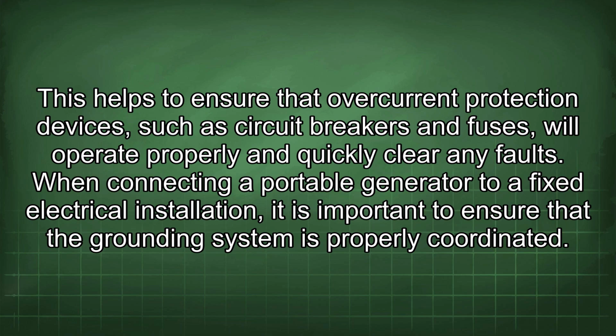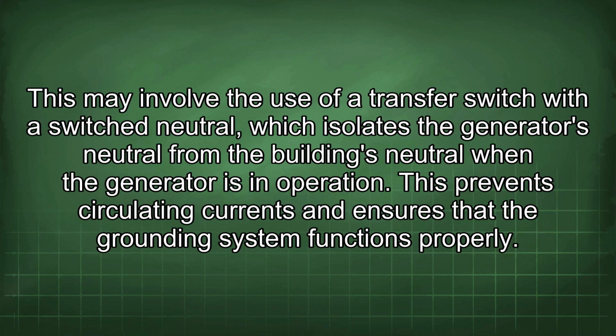When connecting a portable generator to a fixed electrical installation, it is important to ensure that the grounding system is properly coordinated. This may involve the use of a transfer switch with a switched neutral, which isolates the generator's neutral from the building's neutral when the generator is in operation. This prevents circulating currents and ensures that the grounding system functions properly.